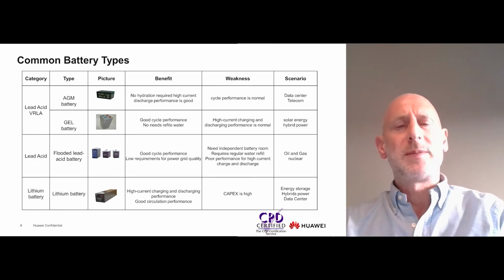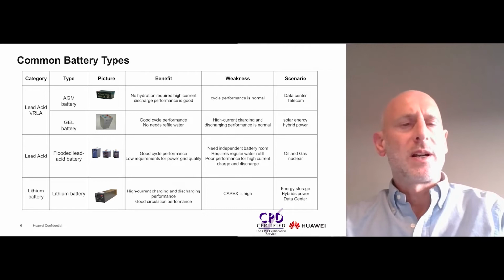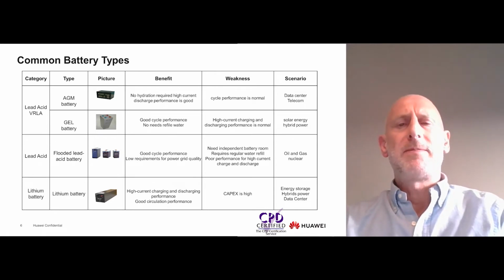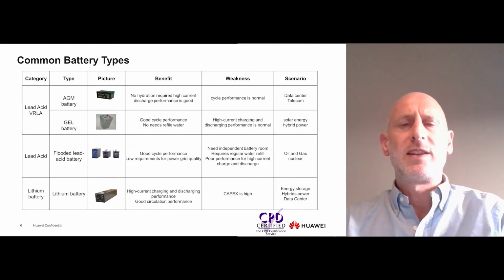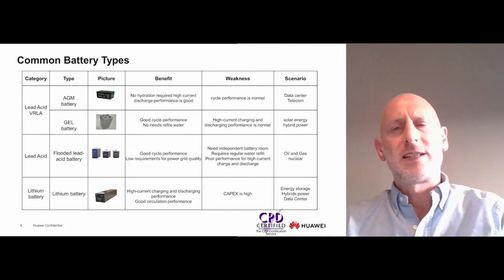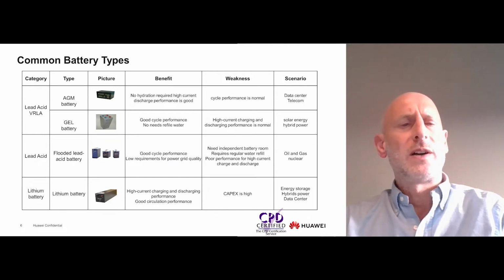There are two primary types of valve-regulated lead-acid (VRLA) batteries: absorbent glass mat (AGM) and gel cell. AGM batteries feature fiberglass mesh between the battery plates, which contains the electrolyte and separates the plates. Gel cells add silica dust to the electrolyte, forming a thick, putty-like gel. Both types of VRLA batteries offer advantages and disadvantages compared to flooded vented lead-acid (VLA) batteries, as well as to each other.